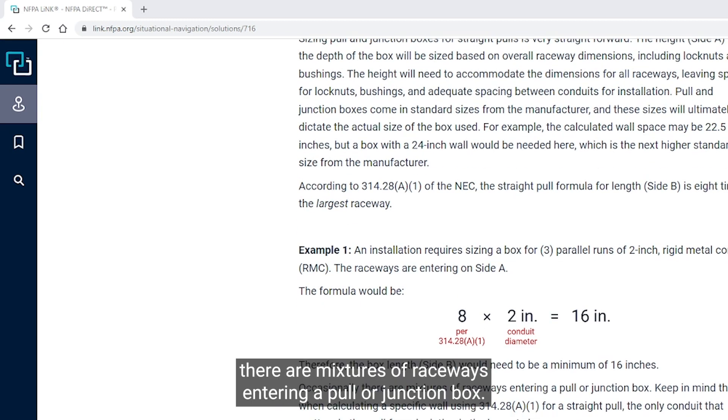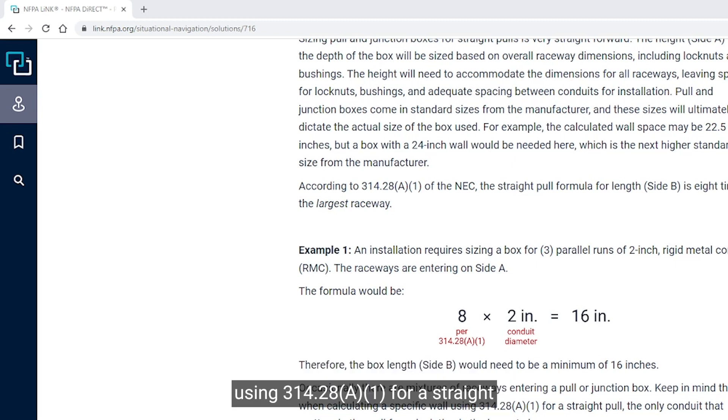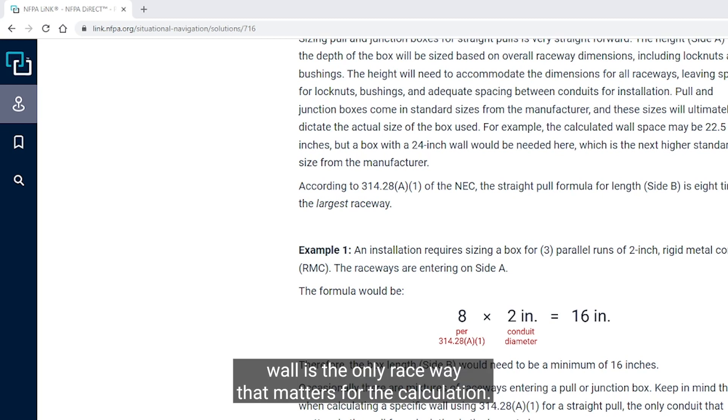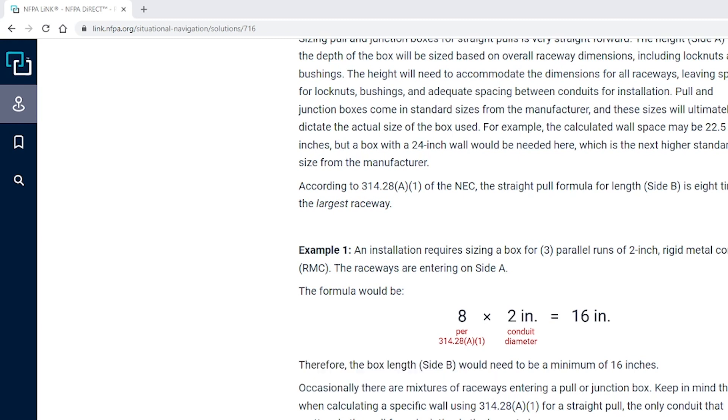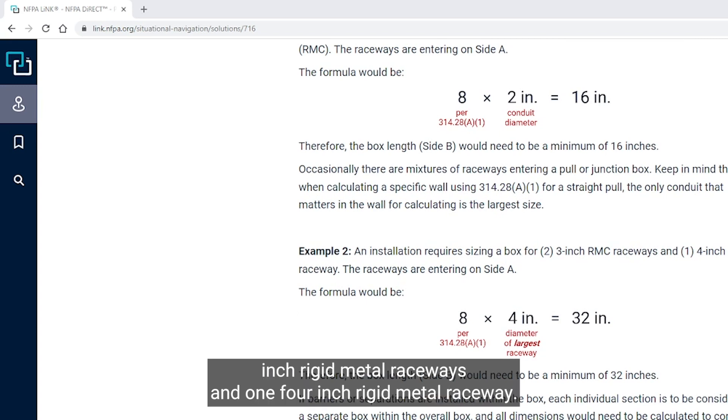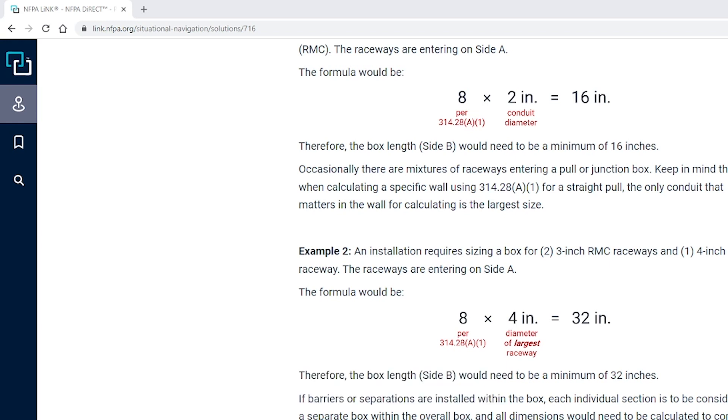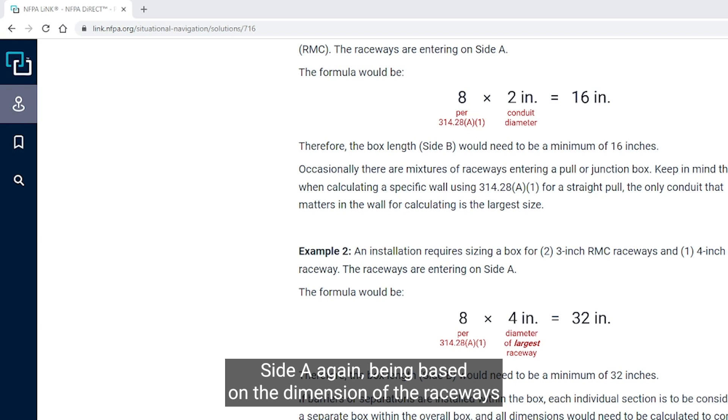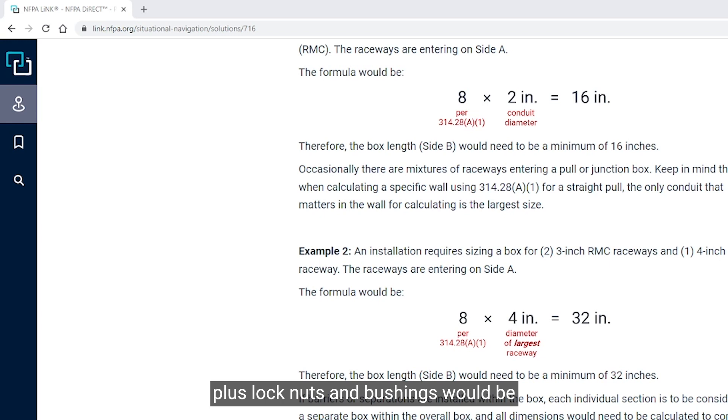Now, occasionally there are mixtures of raceways entering a pull or junction box. Keep in mind that when calculating a specific wall using 314.28(A)(1) for a straight pull, the largest raceway on the box wall is the only raceway that matters for the calculation. For our Example 2, we have an installation that requires a box that will have two 3-inch rigid metal raceways and one 4-inch rigid metal raceway entering on side A. So we're solving for side B, which would be 8 times 4, which would be 32 inches. Side A, again, being based on the dimension of the raceways plus lock nuts and bushings, would be 6 plus 4 is 10, so likely to be a 12-inch tall box. You'd probably have a 32-inch by 12.